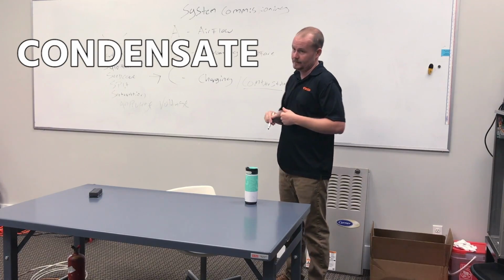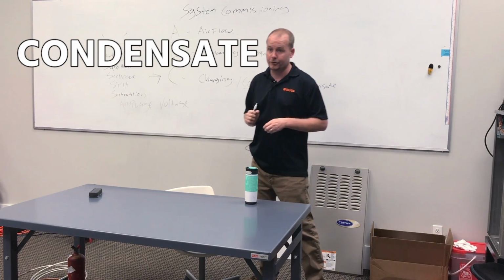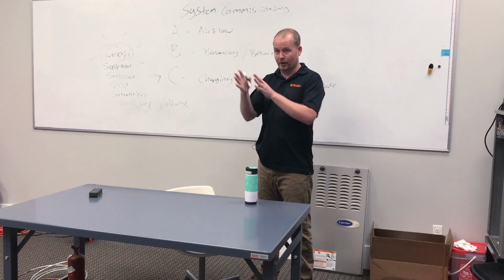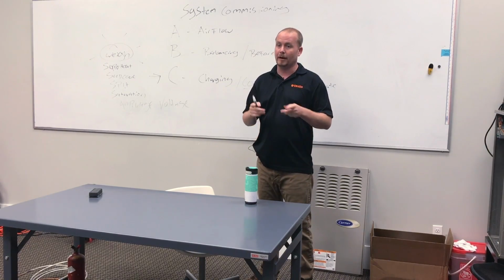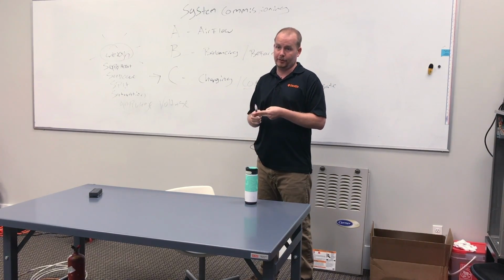And then condensate. Condensate means primarily two things. Is it draining? There are a lot of things that go into making it drain, but is it draining? And does the float switch work? You have to test the float switch to make sure it shuts the unit off, and you have to make sure it's draining.